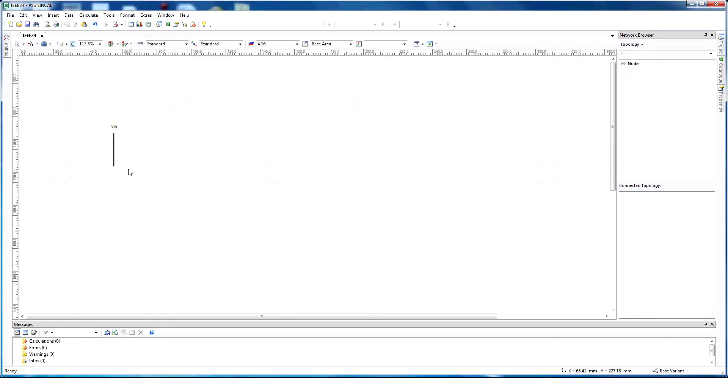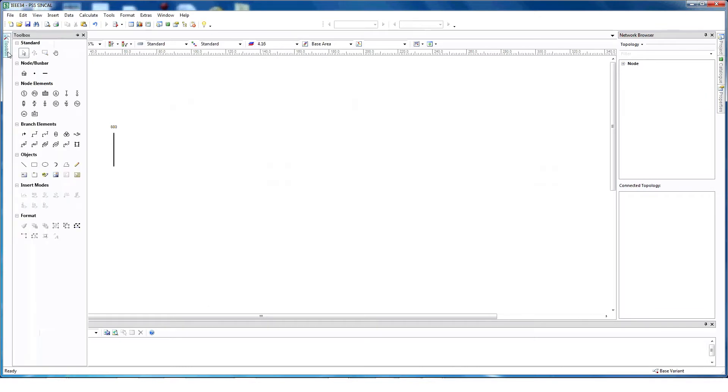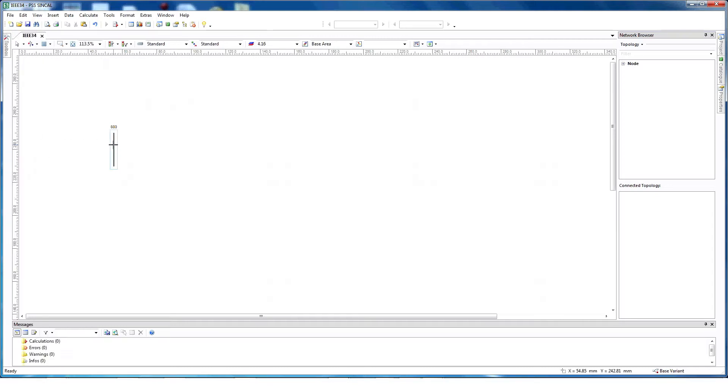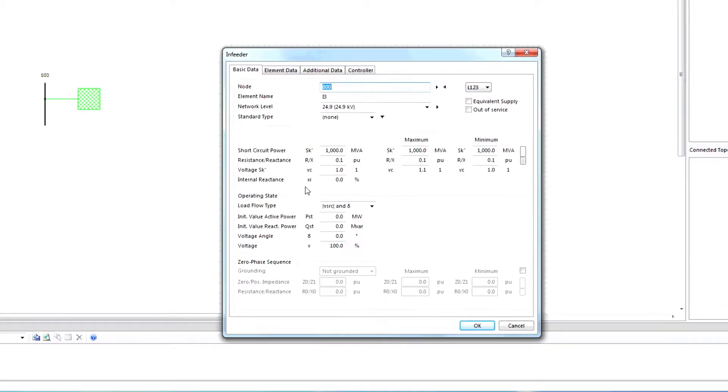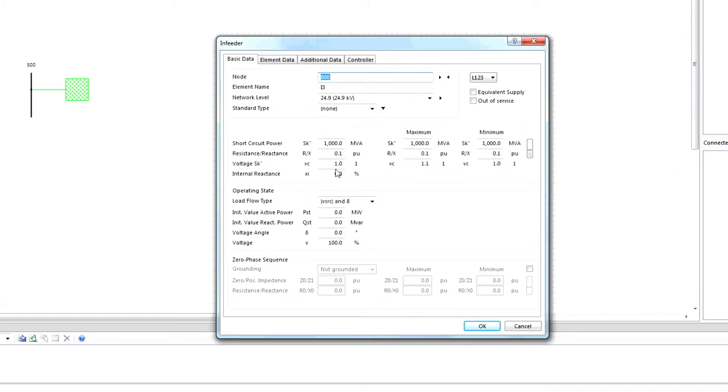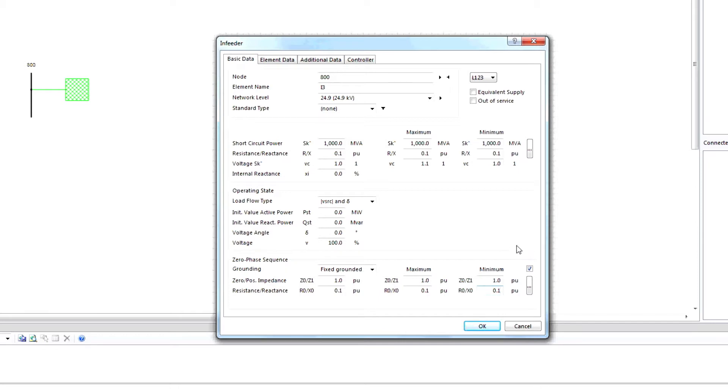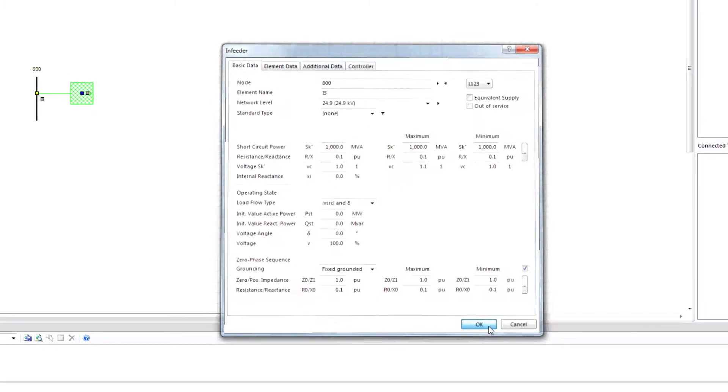Next, create a source model swing. Select in-feeder swing, keeping in mind that the swing bus for load flow fixes the voltage in both amount and angle. Enter other parameter information such as short circuit power, resistance reactance, the zero phase sequence information, and other necessary information. And then click OK.